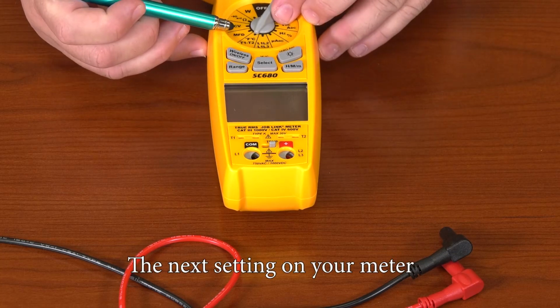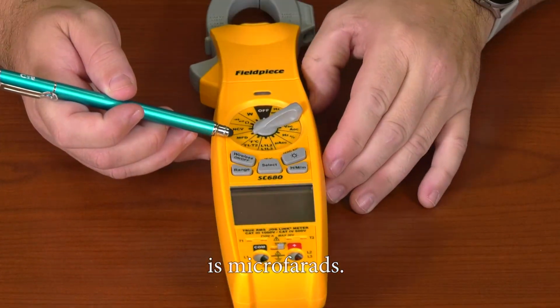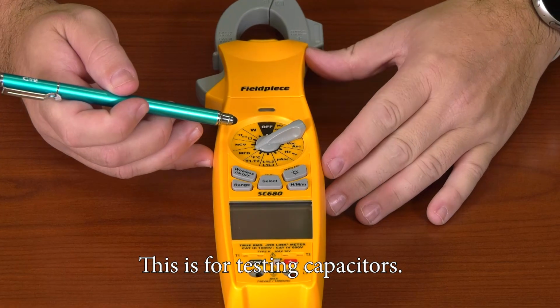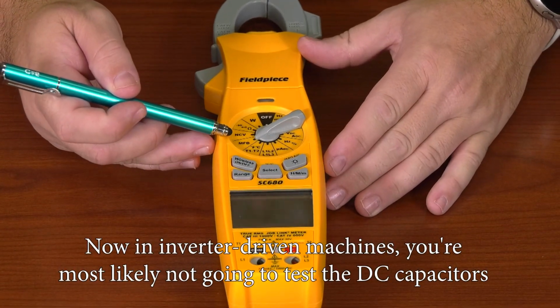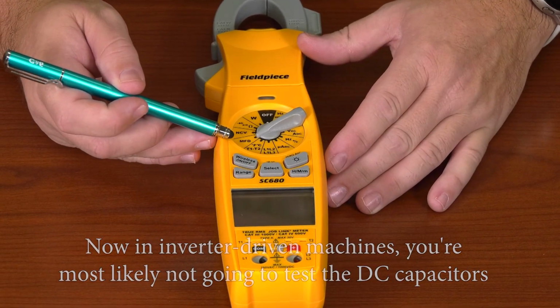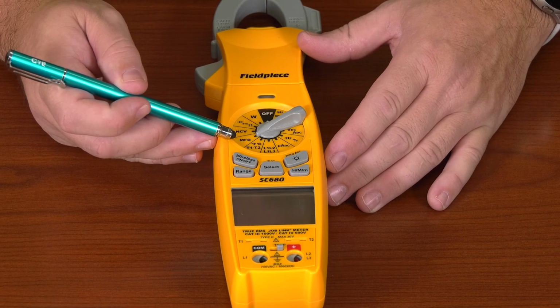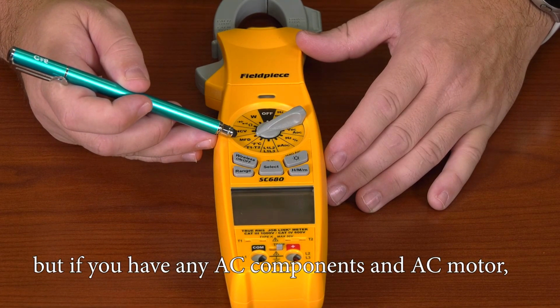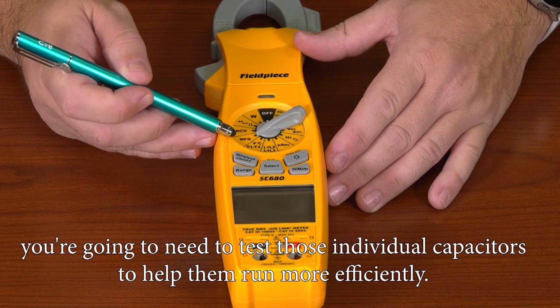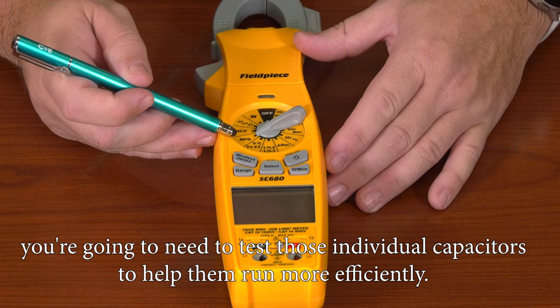The next setting on your meter is microfarads. This is for testing capacitors. Now, in inverter-driven machines, you're most likely not going to test the DC capacitors that are on the control boards. But if you have any AC components, an AC motor, you're going to need to test those individual capacitors that help them run more efficiently.